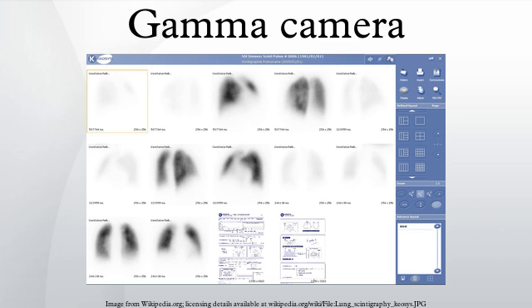The system accumulates events, or counts, of gamma photons that are absorbed by the crystal in the camera. Usually a large flat crystal of sodium iodide with thallium doping in a light sealed housing is used.